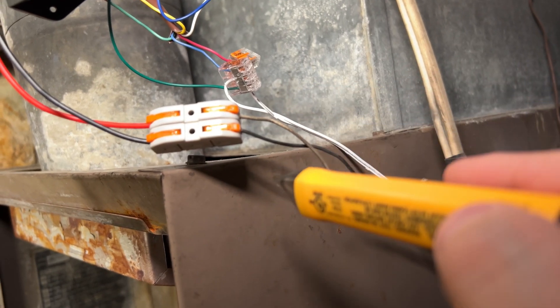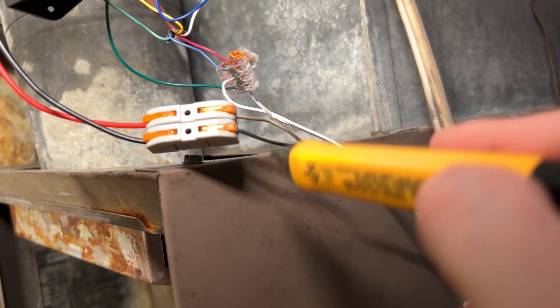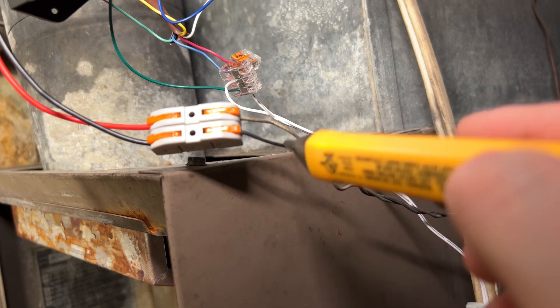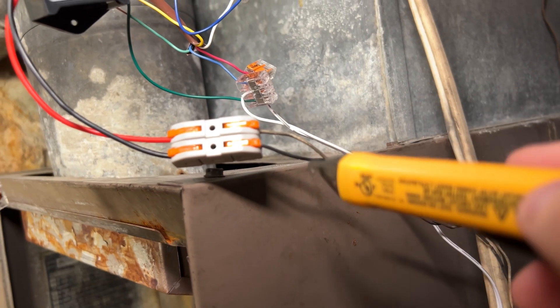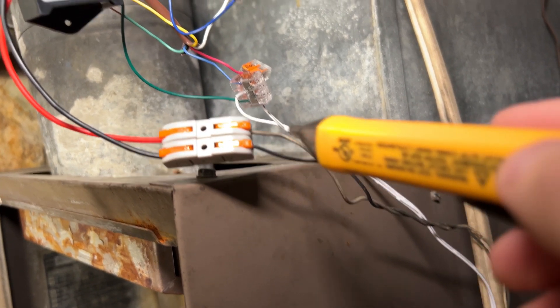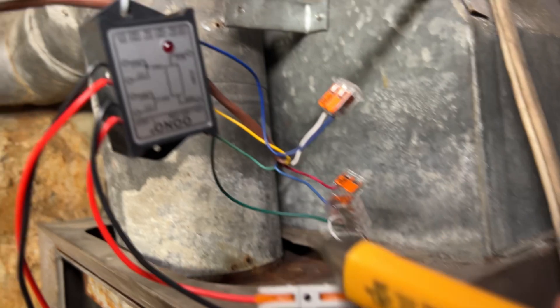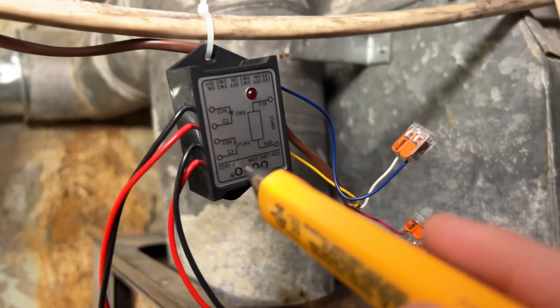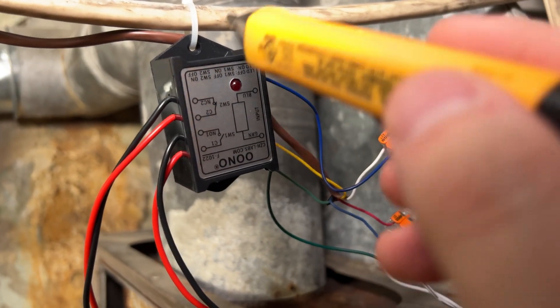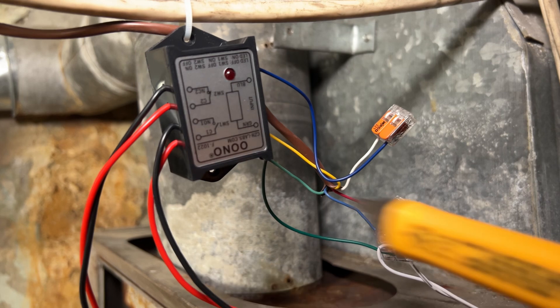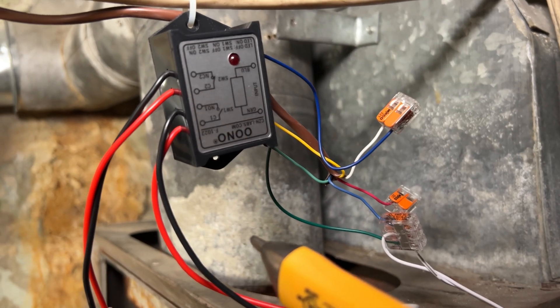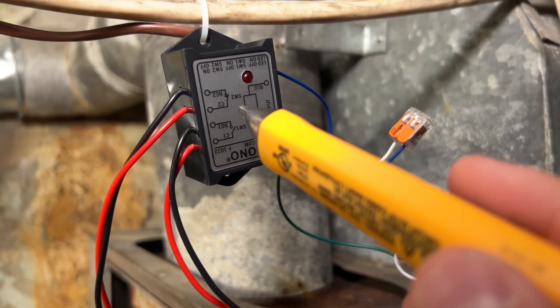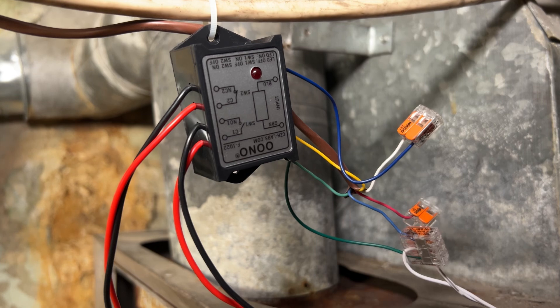Because really in a two-wire system, if we just took the white and black wire and touch them together, we would start up the furnace. It's that simple, there's no sort of magic going on. So that's what the relay allows us to do, is have two separate circuits that are completely isolated, and that happens through a little electromagnet in here.